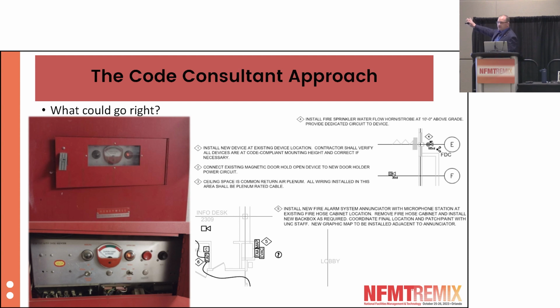Even something like a fire department connection, having a horn strobe at a fire department connection so it's being used and triggered appropriately. Being able to reuse things that have been abandoned - in this case, this is a fire hose cabinet that was abandoned, but they needed a place to put the new fire alarm annunciator. So they were able to capture that, pull out the old fire hose cabinet. That gave them a riser from the basement to the first floor, and they put their annunciator with the audio panel in there. It was a great use of ability to do that.